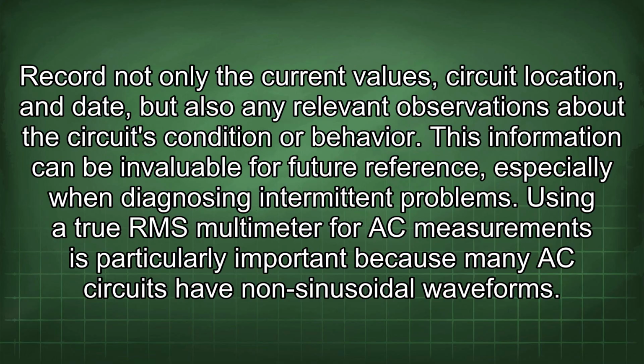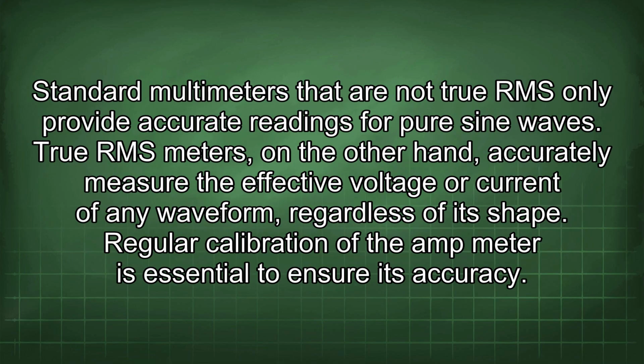Using a true RMS multimeter for AC measurements is particularly important because many AC circuits have non-sinusoidal waveforms. Standard multimeters that are not true RMS only provide accurate readings for pure sine waves. True RMS meters, on the other hand, accurately measure the effective voltage or current of any waveform, regardless of its shape. Regular calibration of the ammeter is essential to ensure its accuracy.